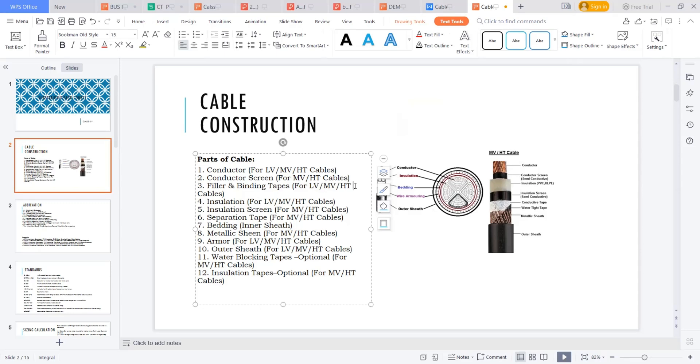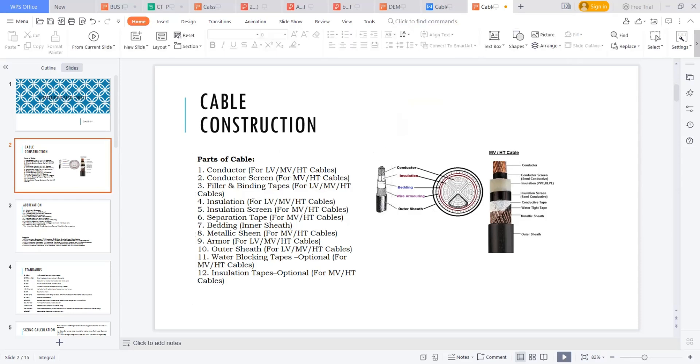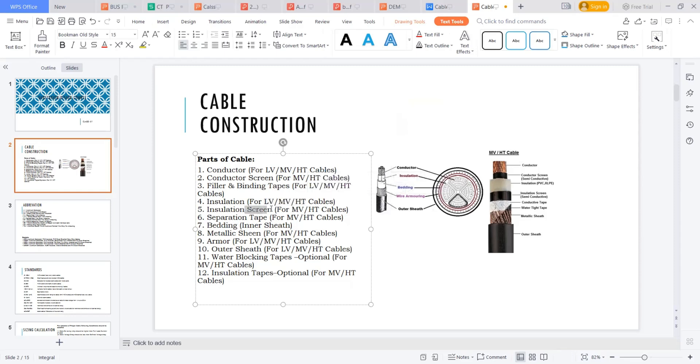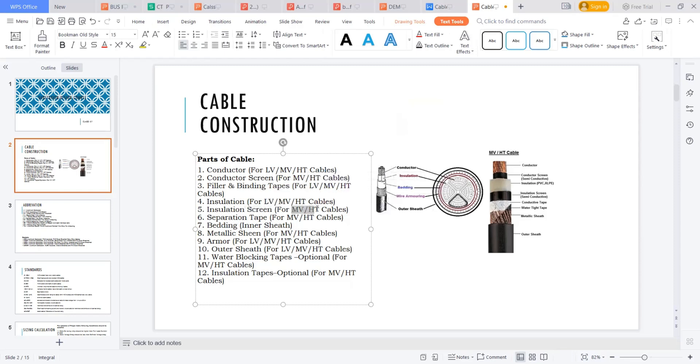The insulation provides core insulation and is applicable for all voltage classes. This insulation could be cross-linked polyethylene or polyvinyl chloride, which is a PVC component. The insulation screen is only applicable for medium voltage and high tension cables. This is also a semiconductor like conductor screen.